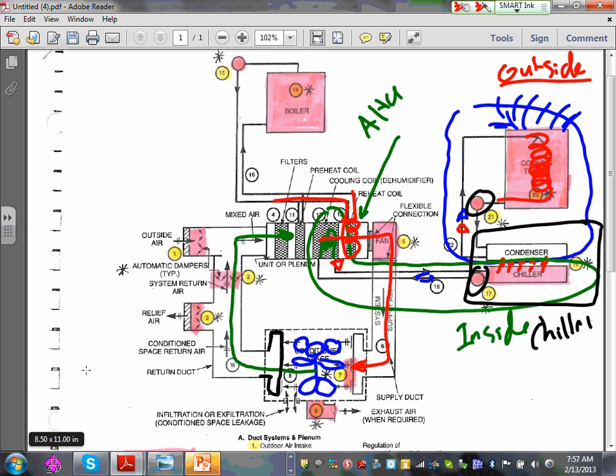We're boiling the water here, and we're circulating the water back into another separate coil inside the same air handling unit, and we're blowing with the same blower inside it. The blower is blowing air into the hot coil, and that's how we get your heat on a day like this in Minnesota. So the air handling unit, like the name implies, guys, handles air, hot air or cold air.